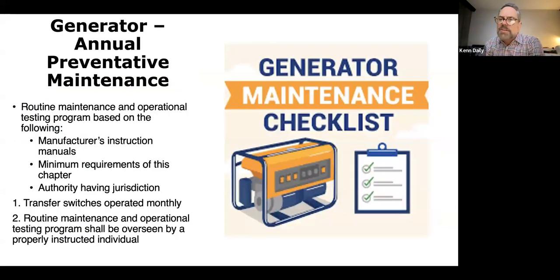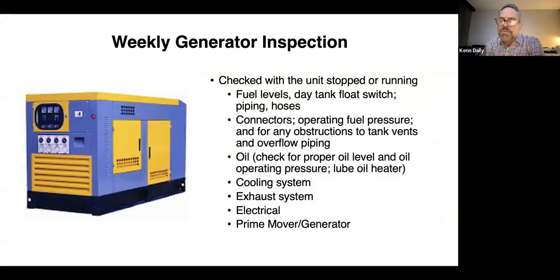Generator again. There are a lot of things for generator preventive maintenance: annual, weekly visual, monthly exercise. The visual weekly is whether the generator is running or not. There's no requirement for the generator to run weekly. So you're looking at the generator from the prime mover back to the transfer switch, checking the fuel level, checking the belts and hoses, checking inside, making sure that there are no new bird's nests or whatever, no family of bears or raccoons have moved in, kind of thing. But the whole idea is that you're visually inspecting it weekly.